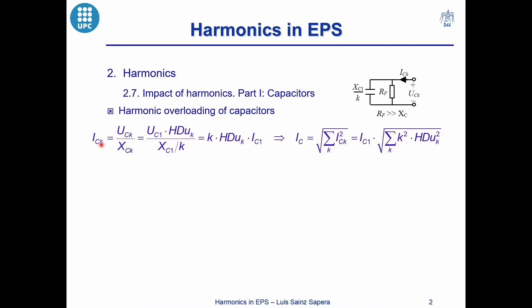These harmonic currents increase the RMS value of the capacitor current. If the supply voltage does not contain harmonics, the RMS value of the capacitor current is equal to the fundamental current. While if the supply voltage contains harmonics, the capacitor current depends on the fundamental current by a factor depending on the square of the harmonic order and the harmonic voltage distortion.